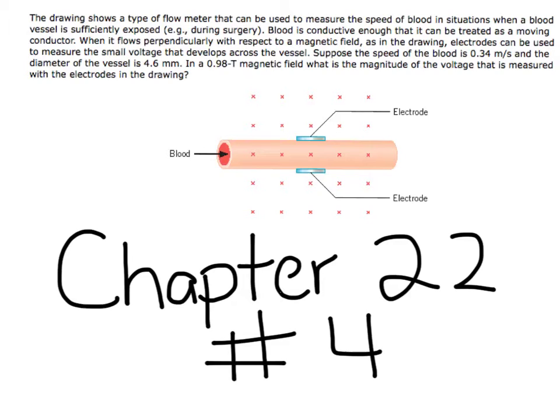The drawing shows a type of flow meter that can be used to measure the speed of blood in situations when a blood vessel is sufficiently exposed, for example during surgery. Blood is conductive enough that it can be treated as a moving conductor. When it flows perpendicularly with respect to a magnetic field as in the drawing, electrodes can be used to measure the small voltage that develops across the vessel.